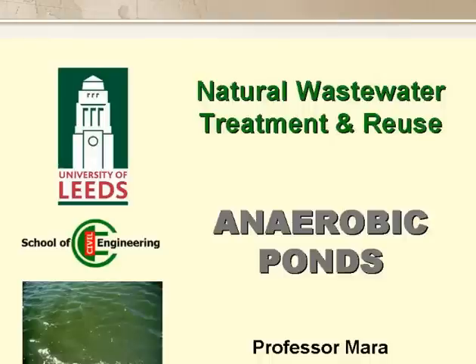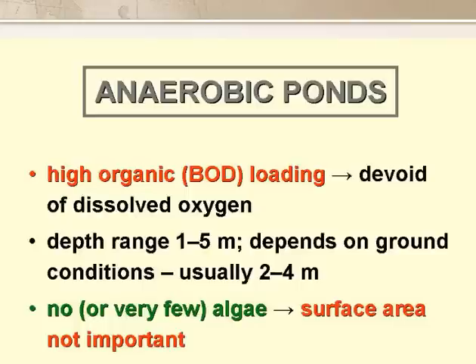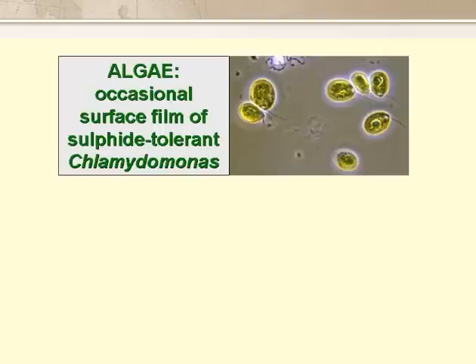In this presentation we're going to look at the design and performance of anaerobic ponds. These ponds have such a high organic loading, or BOD loading, that they do not contain any dissolved oxygen. They're usually quite deep, often two to four metres deep, and they contain no, or very few, algae, although we occasionally come across a thin surface film of Chlamydomonas, which is a sulphide-resistant alga.